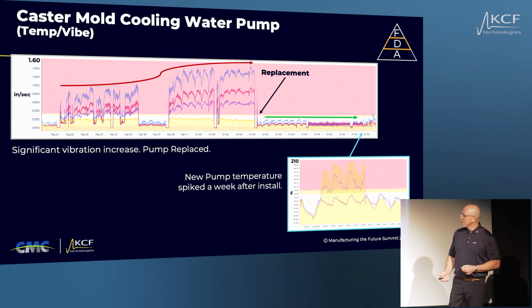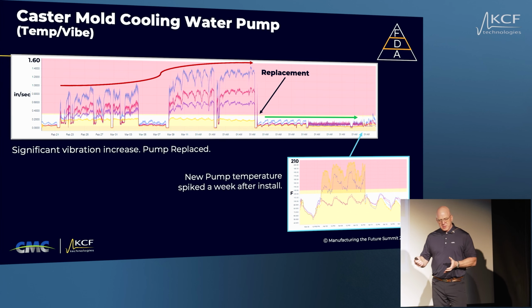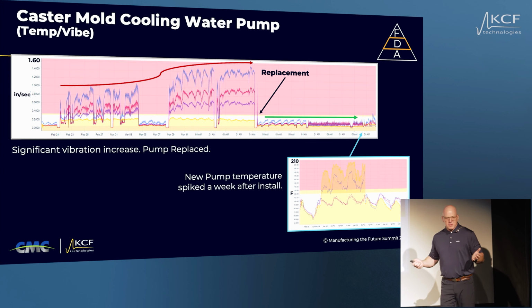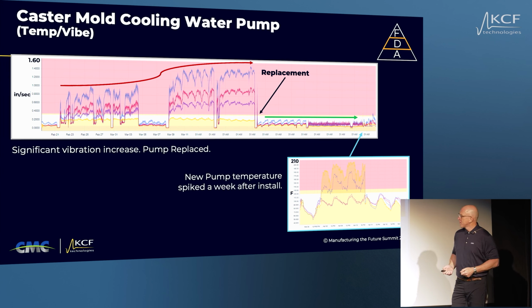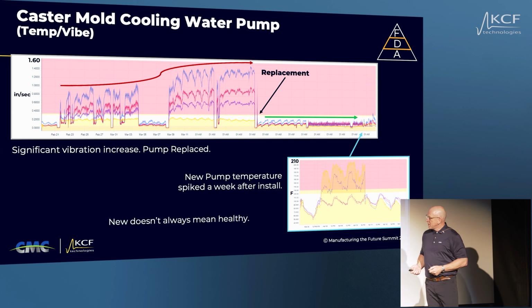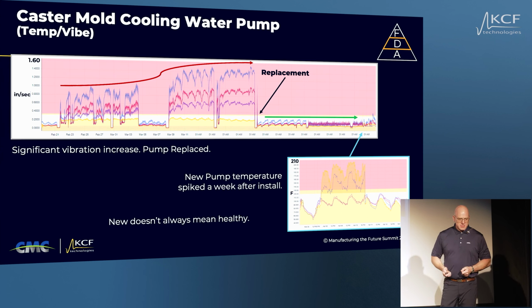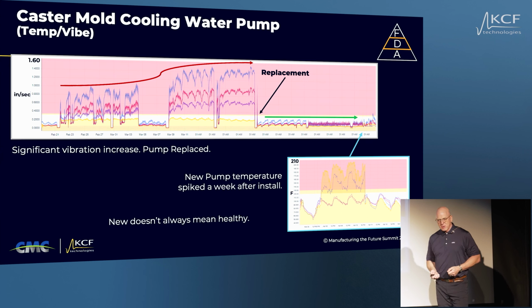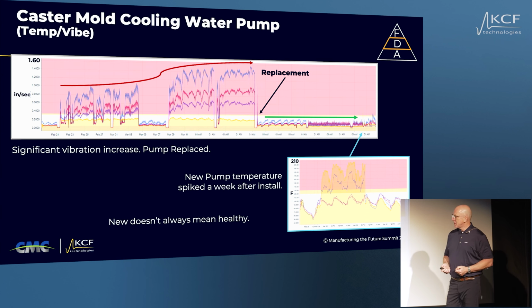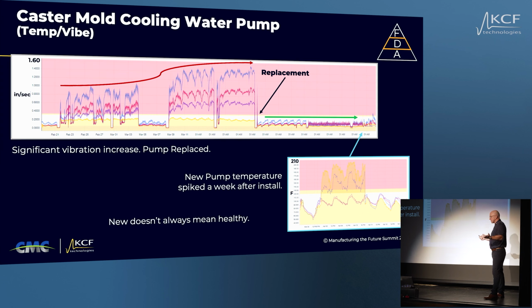Shut the pump down, and the plastic fan on the back of the motor had kind of disintegrated. It had just blown to pieces. There was no cooling on that motor, and it had only been in use a week. So new doesn't always mean healthy. Just keep that in mind. It was a really good win for us, and it was in the pilot stage, this one. So the skeptics, when you show something like that, they totally get it.